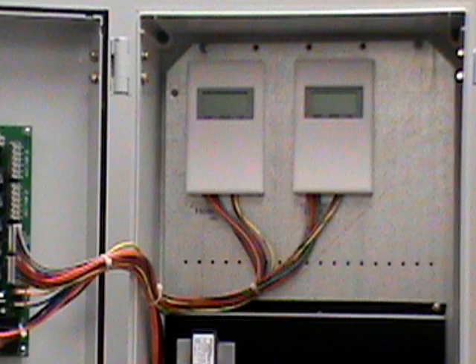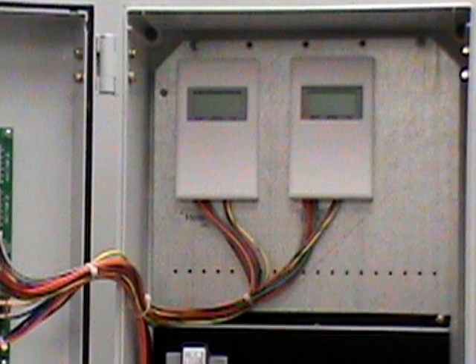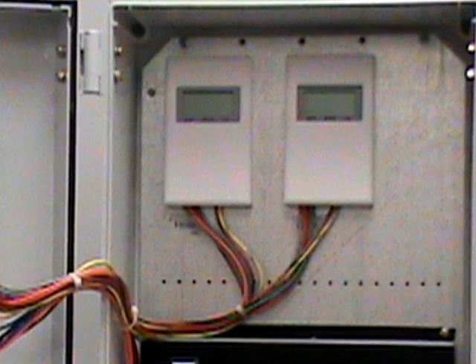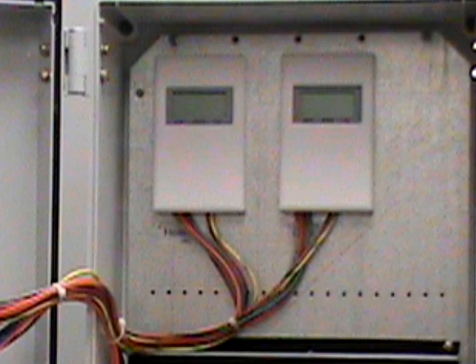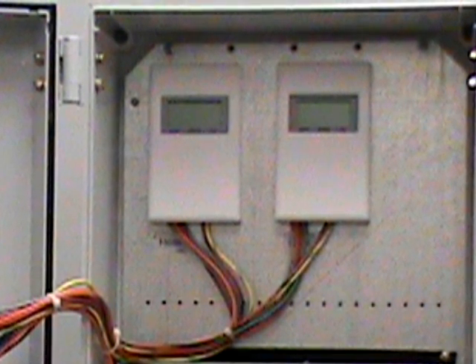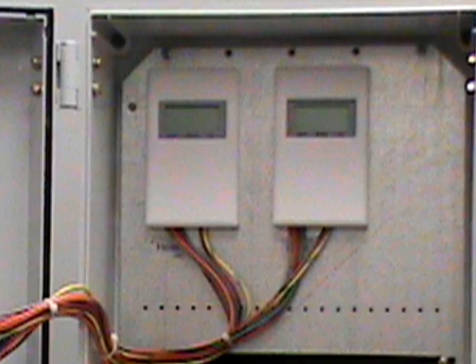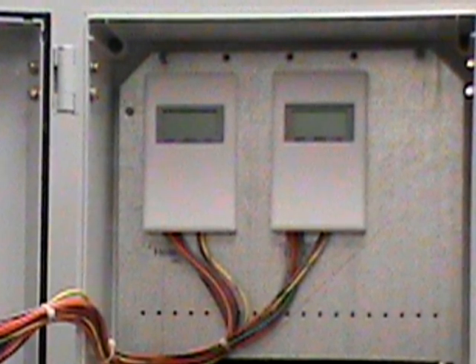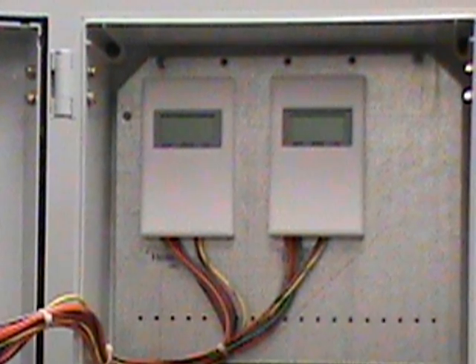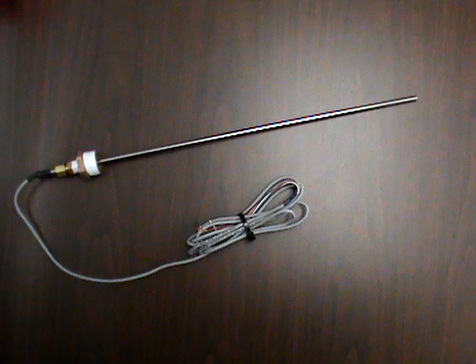Terra-Therm pre-programs each controller for a typical system. However, changing temperature set points, differentials, and delay times are simple and easy to do. If you do experience any difficulties, Terra-Therm technical support is available to assist you with fine-tuning and making adjustments for your unique applications. Included with each Terra-Therm hydronic control module is a stainless steel dual sensor temperature probe, which is used to monitor the buffer tank temperature.